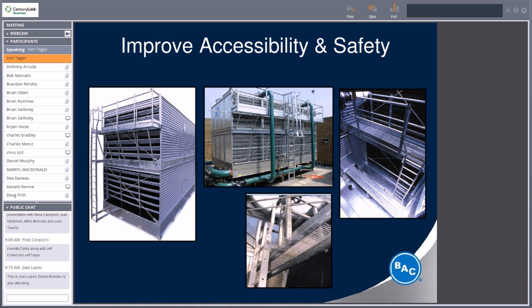Here's an area that I think gets neglected in the design phases and the buyout of cooling towers. These are benefits to the owner. As you can see on the side going from left to right, we have some external service platforms that allow you to inspect the hot water distribution basins on top of the tower without actually having to get on top of the basin. As you move over to the right, you can see the internal service platforms that allow you to work on the belts, the gears, remove a motor without having to be hanging off a ladder. It's really for the safety of you, the maintenance personnel.